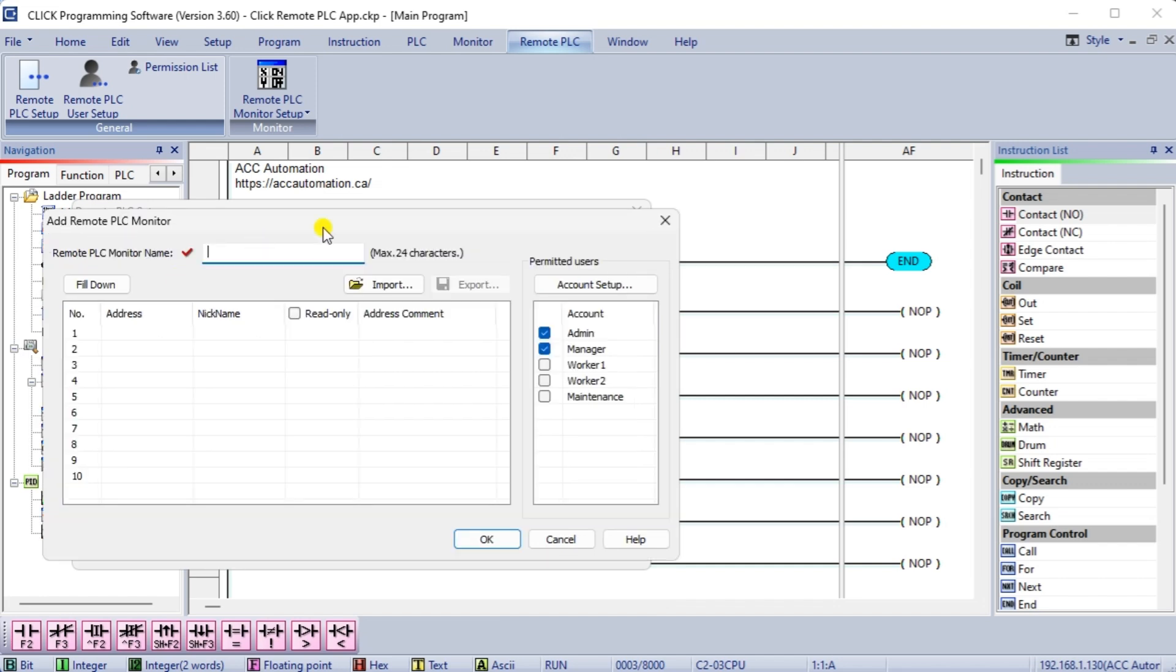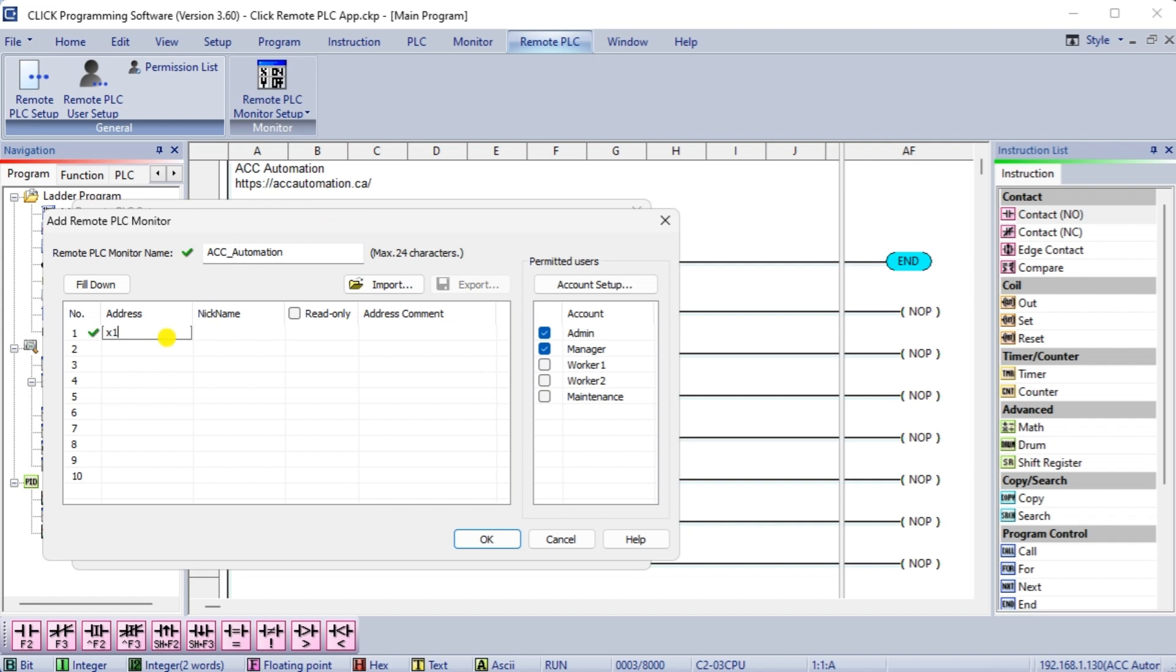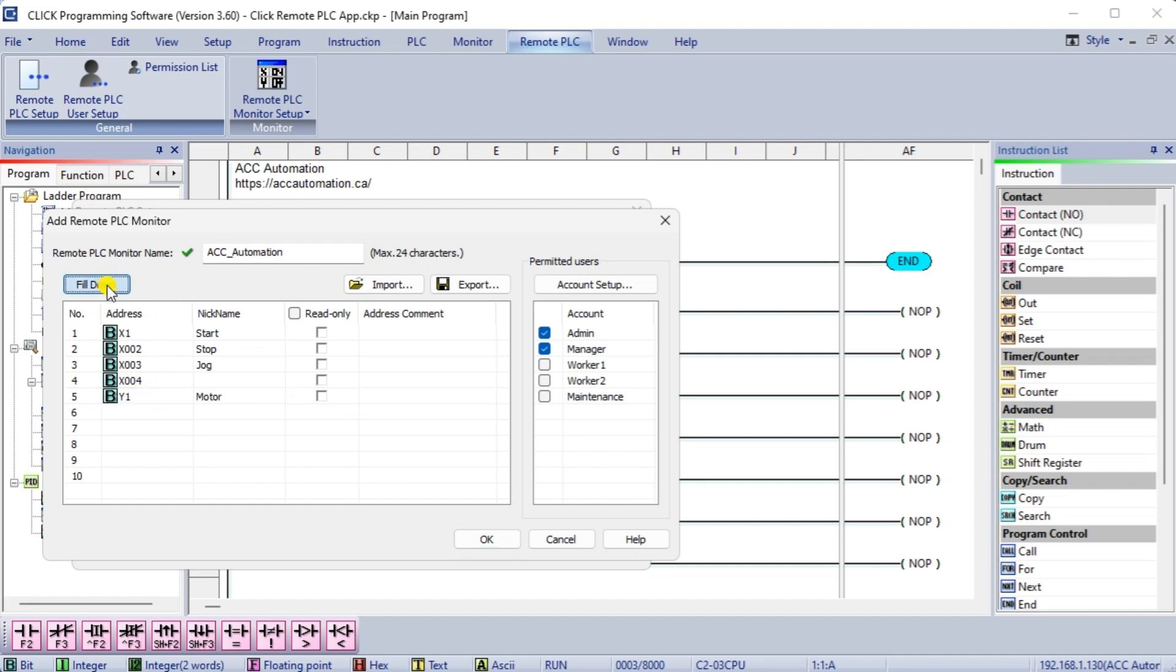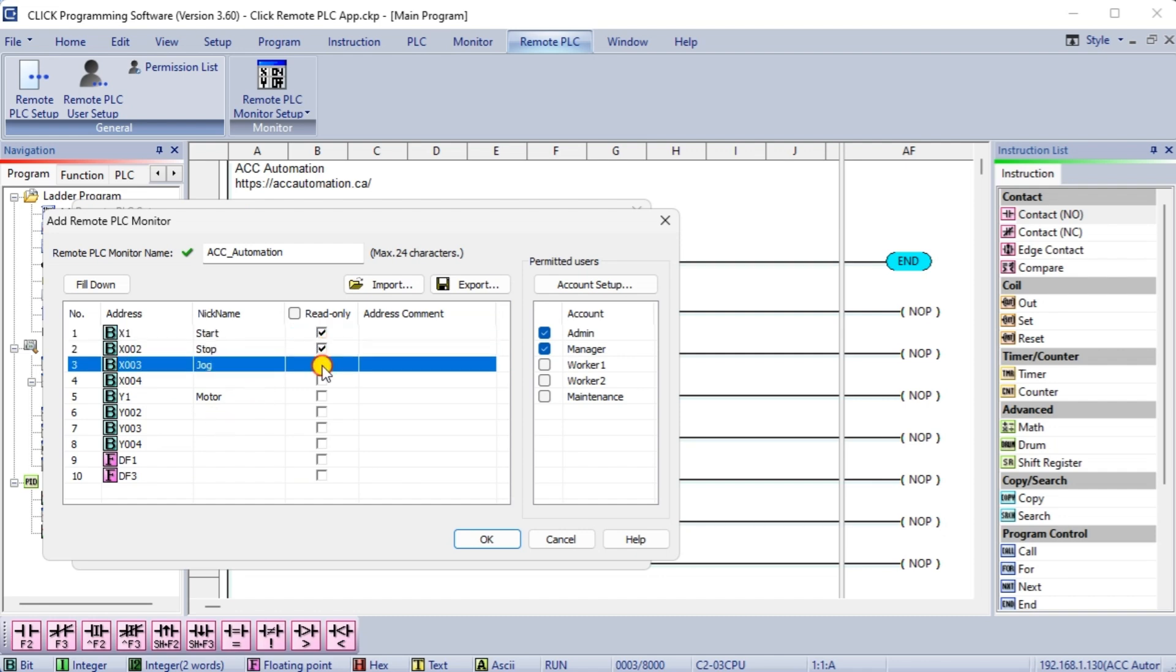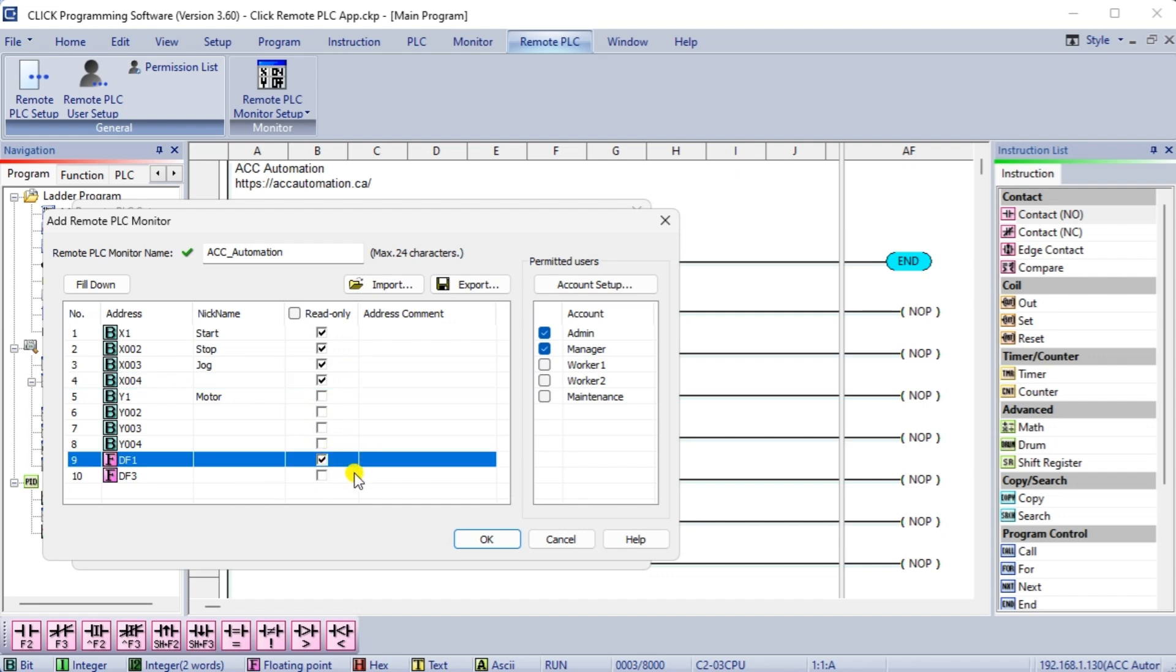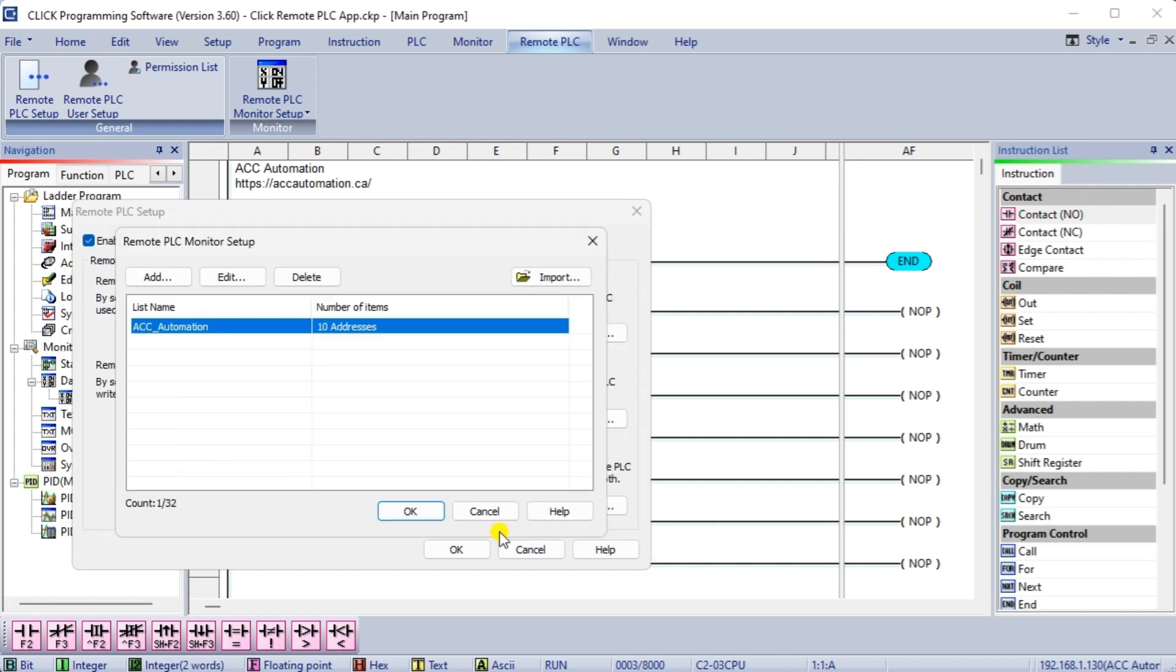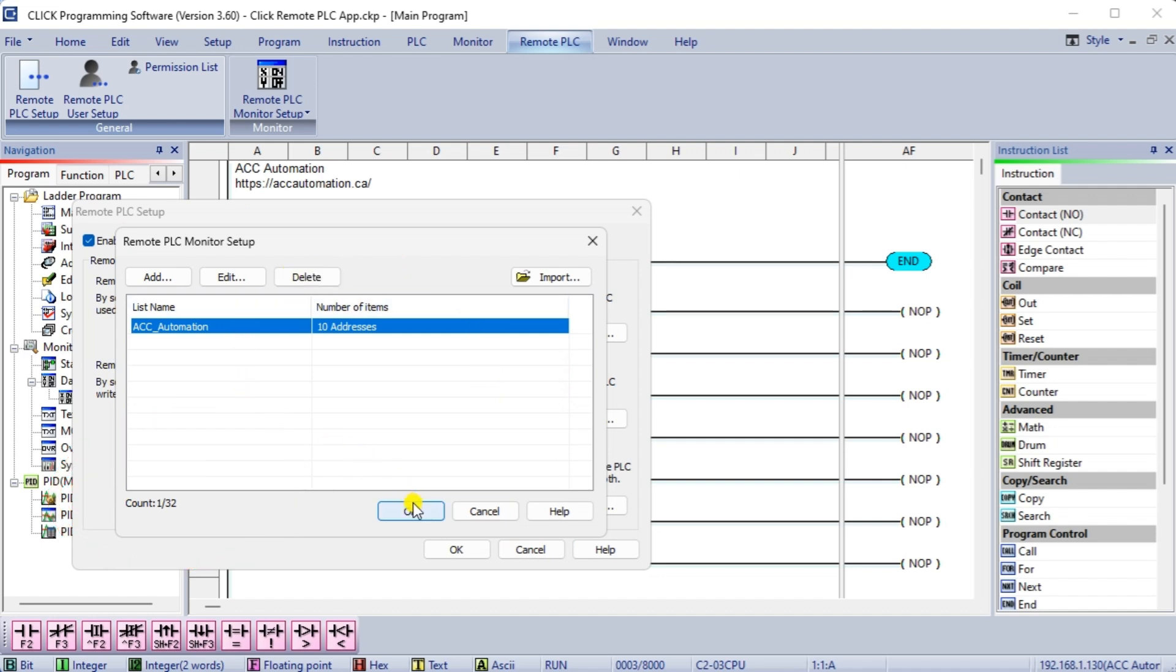This will now display the add remote PLC monitor window. Select the remote monitor name. We can now add addresses we want to monitor and control in the PLC. Use the fill down button to list consecutive addresses in the list. We will enter all of the discrete inputs and outputs of the PLC and the first analog input and output. Set the read only for the addresses we do not want to be changed. In our case, these are discrete inputs and analog inputs. We can set the permitted users of these addresses. Select ok. We can now set up to 32 monitor items with 10 addresses each for the connected click PLC. Select ok.